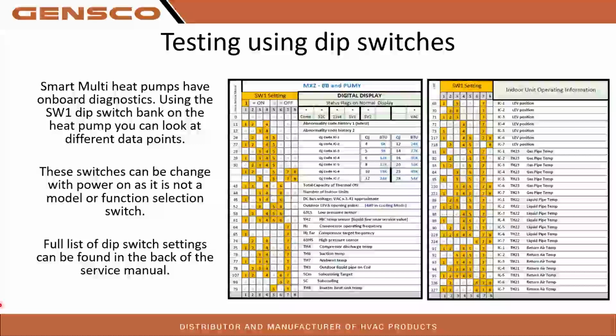And when you start it up after that, it will go get a fresh look at all the addressing. So as far as clearing the error codes, SW2-3 with the power on, you can do that at any time. It only needs to be left on for about 5 seconds, and then you can turn it back off. If you ever look at the abnormality code history and flip that dip switch on 1, 2, and 4, and you get an 8,255, that is not an error code. That is a code that tells you there are no stored error codes, which is kind of weird.